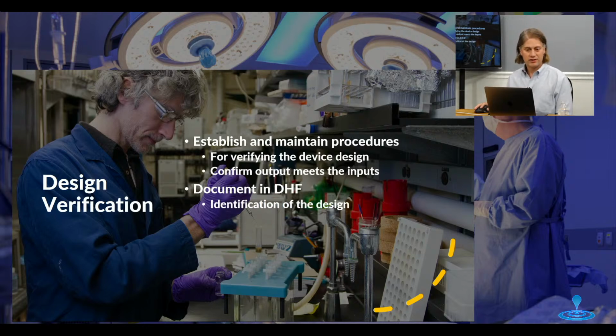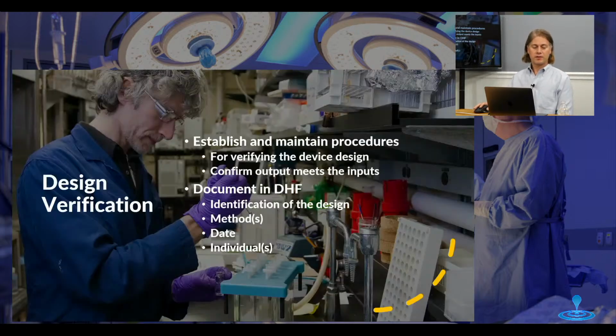including identification of the design, the methods used to do verification, the date, the individuals performing the verification, and that's design verification. If you're surprised at how simple that is, don't be. There's a lot that goes in under the hood there. There are best practices, there are standards, there are third-party test houses, there's guidances for writing test methodologies. We're not saying this is all that there is to medical device verification testing.